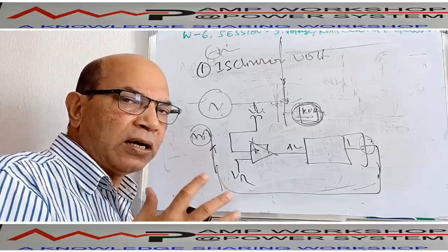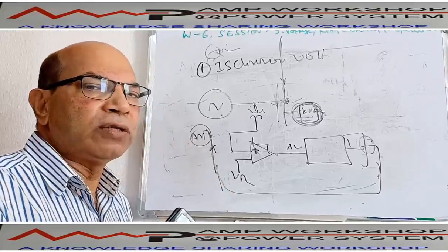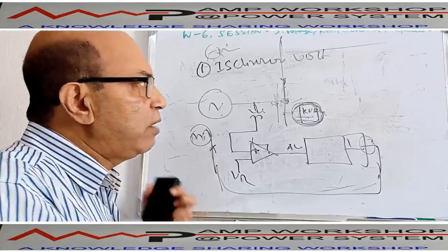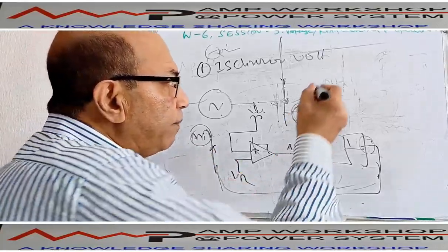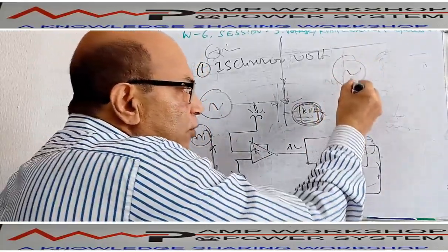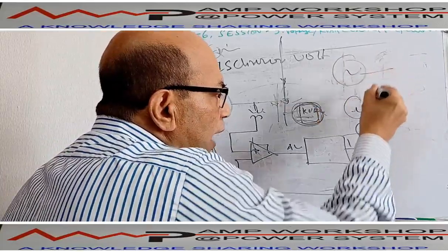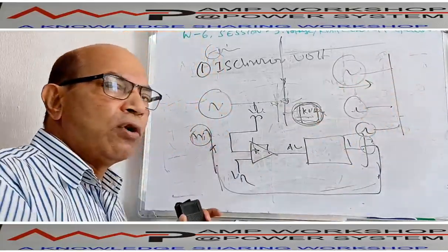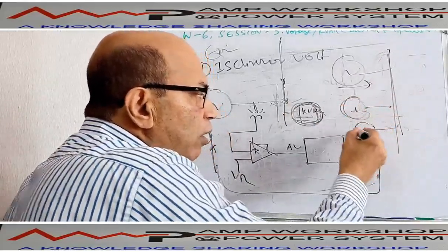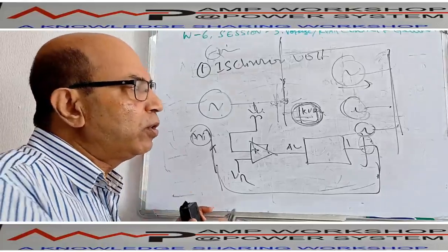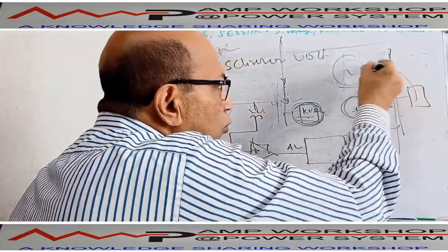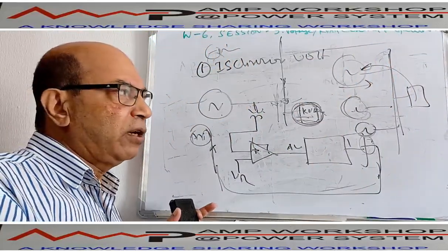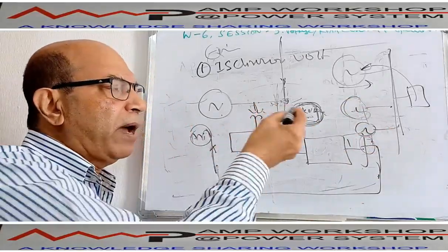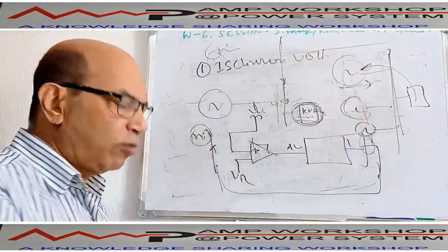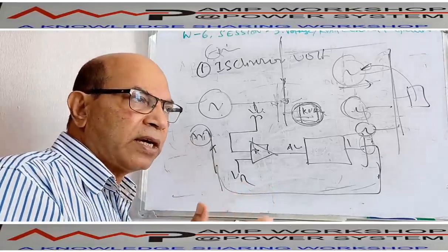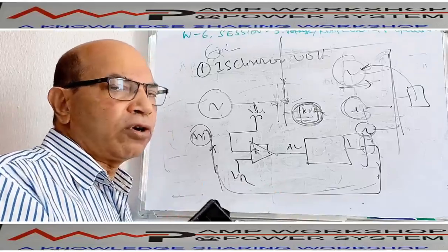Otherwise, if the machines are identical, with identical controllers, in that case we can use the isochronous mode. Another option is to use isochronous mode with a two machine system or multi machine system if one of the machines is very big in comparison to the others. In that case, the big machine will run in isochronous mode, which will maintain the bus voltage. And the other generators will work in droop mode, not in isochronous mode. Whenever extra load comes on the system, all the additional load will be taken by the main generator. The other machines will take load only with manual intervention. That way also we can run isochronous mode. But it is always preferable that multiple machines of similar size, or with minor difference in size, should not be run in isochronous mode.